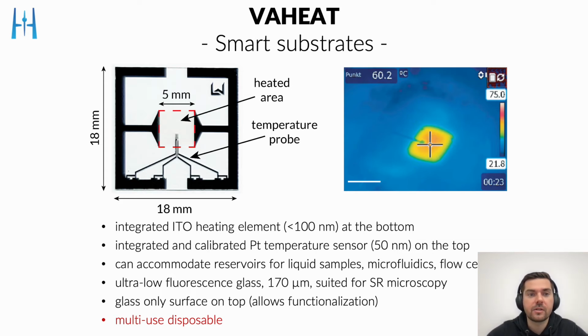The image is shown here. These are the cover slips with integrated sensors that have a 5 by 5 millimeters heated area and a tiny temperature probe integrated in that field of view. And this allows you, with direct feedback, to set the temperature to any arbitrary value that you would like to have, without affecting the imaging quality. The substrates themselves are multi-use disposable, so you can reuse them and clean them, but at a certain time they might get destroyed.